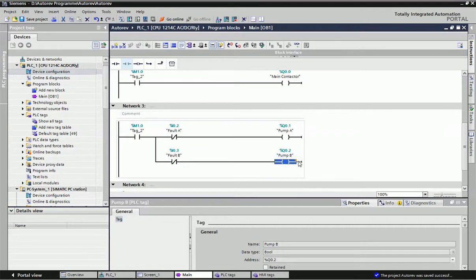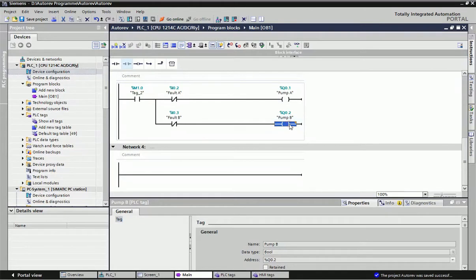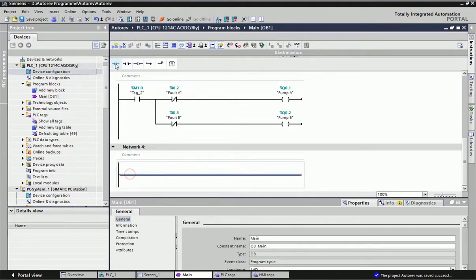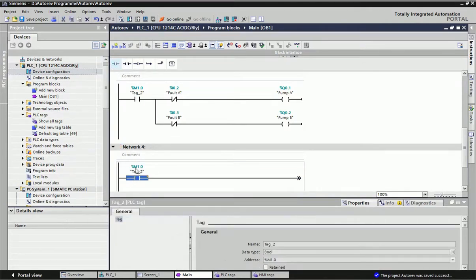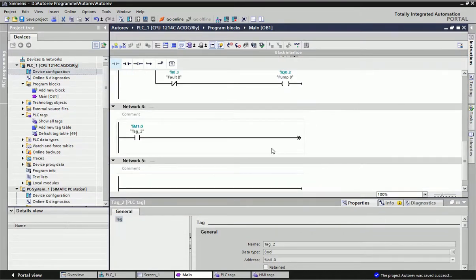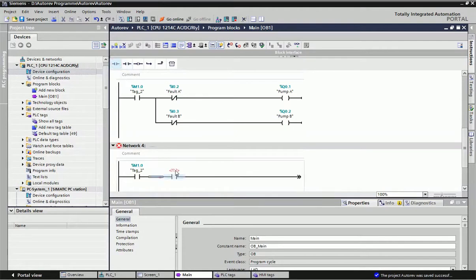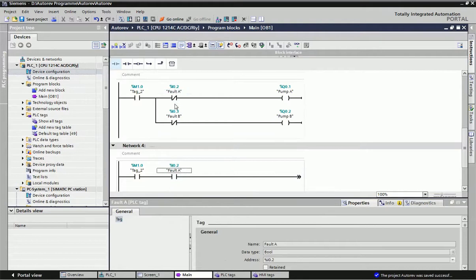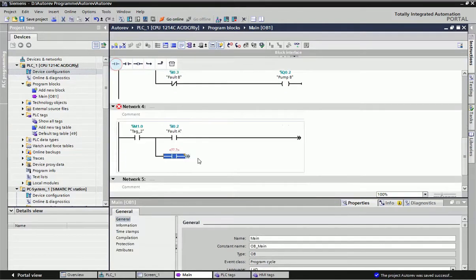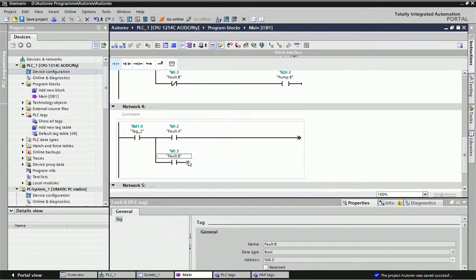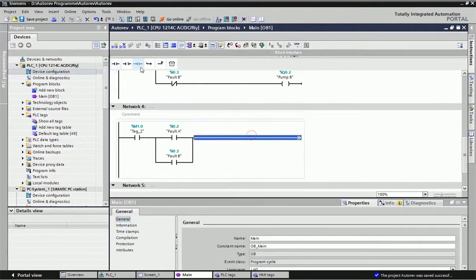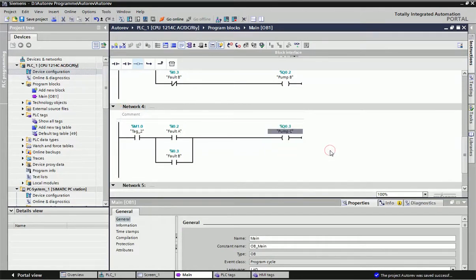As per the second condition, when pump A or B fails, standby pump C will turn on. We again use memory bit M1.0 — it is mandatory that when M1.0 is on, only then should the system run. Here I use fault A and fault B as open contacts to enable pump C. When fault A occurs, that open contact closes, enabling pump C. Either fault A or fault B triggers pump C. For failing pump C, we also add a fault C contact.